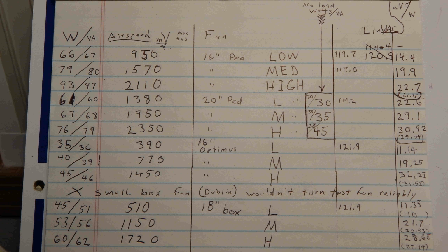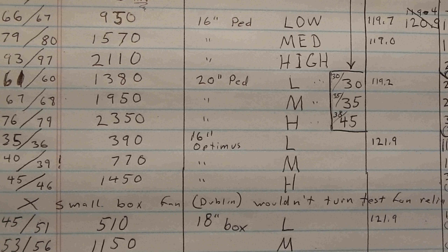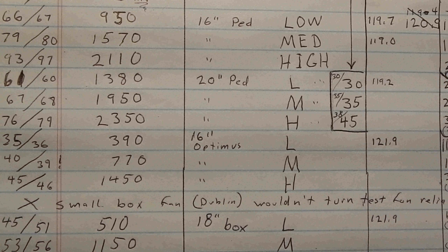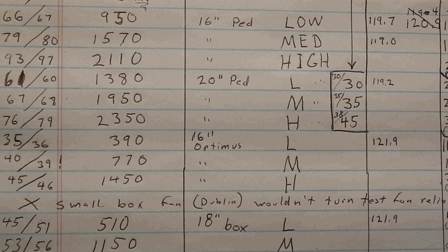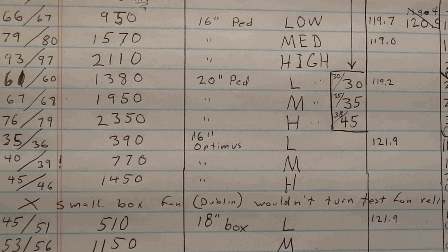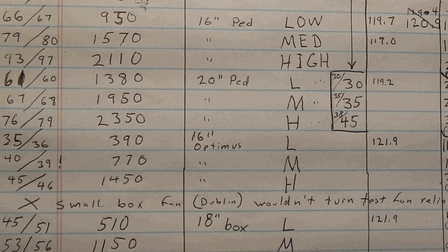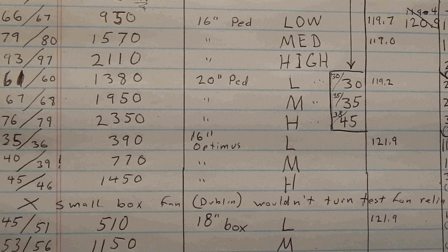But you can see 14 goes up to 22. So my efficiency, bigger the number the better. My efficiency isn't cut in half on low speed, but it's down there. You look at this fan, it's way down there. I should have done the percentages, I suppose. But it's at least 25% or worse, you know, efficiency-wise.